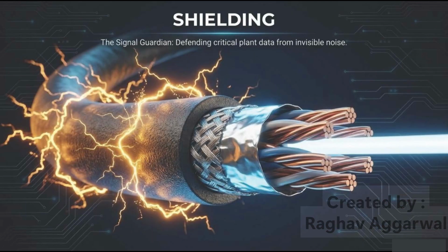Shielding is described as the signal guardian. Its purpose is to defend important plant data from invisible electrical noise. Many industrial instruments generate extremely small signals. These signals may represent temperature, pressure, flow, or other critical process measurements. Electromagnetic interference, often called EMI, can introduce unwanted electrical noise into those signals. When this happens, measurements may become inaccurate and control systems may respond incorrectly. Shielding acts as a protective barrier around signal conductors. Instead of allowing interference to enter the signal path, the shield helps capture unwanted noise before it affects the measurement.